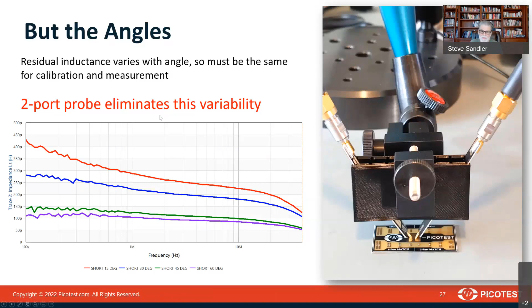So one thing that you can say about the two-port probe is that having the probes very close together does mean that there's coupling, but the coupling is very well fixed. It's not variable. And because it's fixed, it becomes possible to calibrate that out.